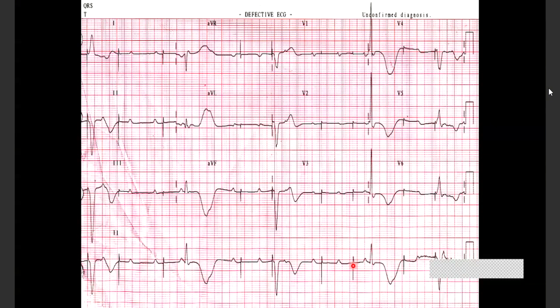So obviously there's a problem with the output. That means the battery seems to be at fault. It's not pacing regularly. It's not producing spikes regularly. If the battery was normal, it should have regularly produced spikes. Here at 75, it should have produced a spike somewhere here. For some reason, it's not producing a spike here, and it's producing a spike here at around 50. This pattern seems inconsistent, sometimes at 50, sometimes at 75. It's not consistent. So obviously, I would suspect a battery problem here, that the battery is depleted. As I told you, when the battery is depleted, the output becomes irregular.